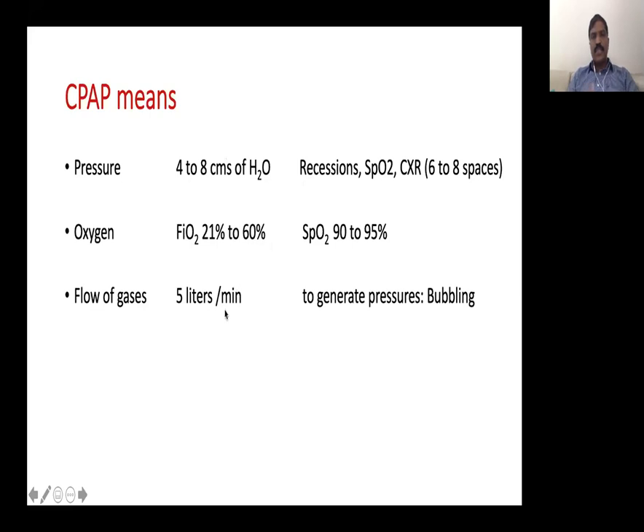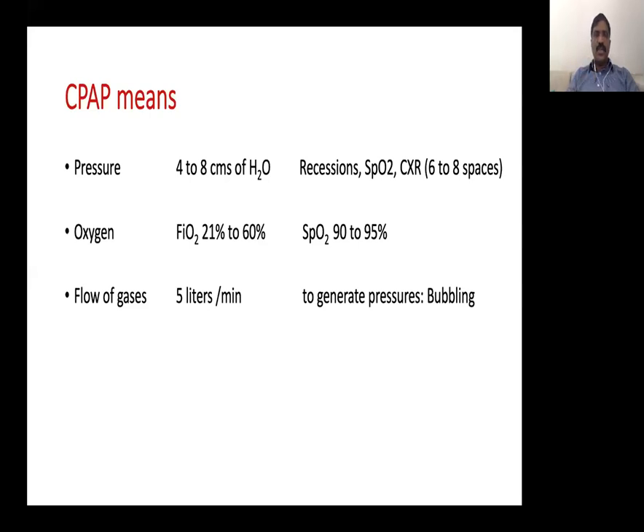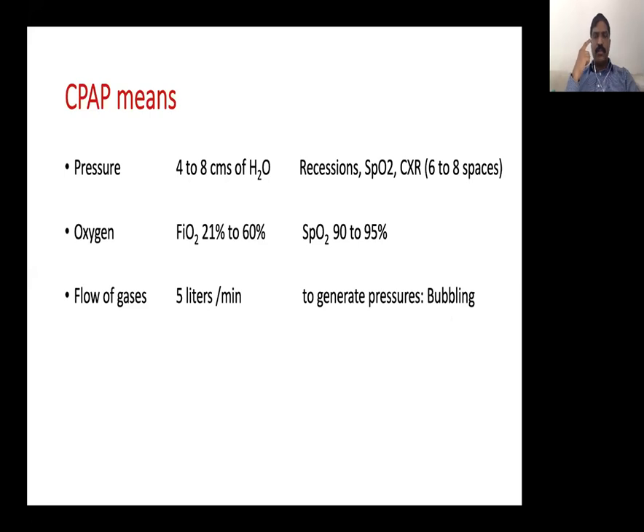The third component is CPAP flow. We need gas flowing across the nose to build pressure in the circuit and in the airway and lungs. Flow is mandatory across the nose for delivering pressure. How do we know if flow is available? By looking at the bubbles in the bubble chamber, or by measuring pressure at the nose. In bubble CPAP, bubbles in the bubble chamber confirm that flow is adequate.